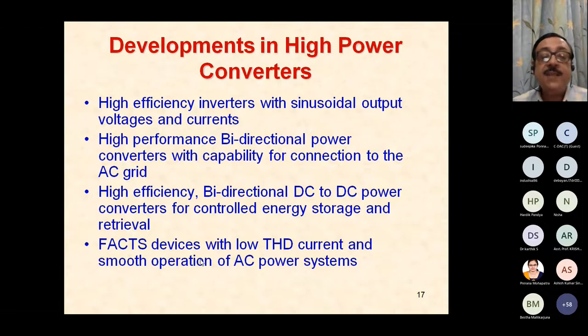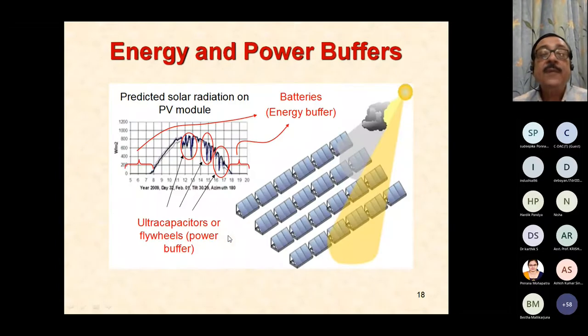FACTS devices, or flexible AC transmission system devices, are required with low total harmonic distortion of current and smooth operation of AC power systems, because we are connecting so many items into the line and most of these power electronic converters are injecting harmonics and VAR into the system. We need to take care of these aspects by adding FACTS devices to the line.